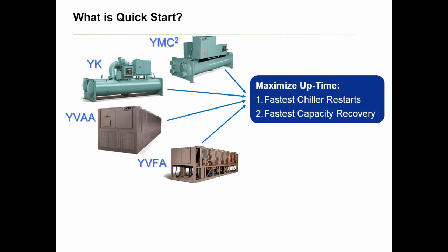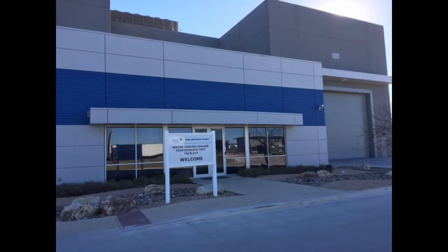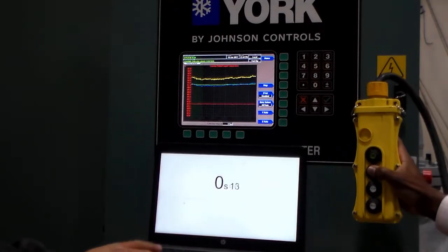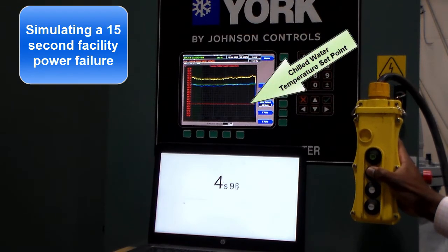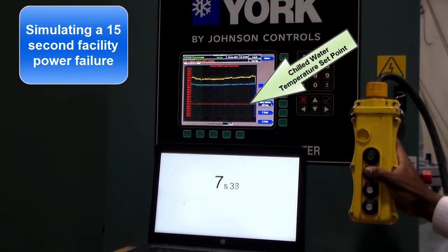To better explain, let's take a look at it in action at the Customer Center of York's Chiller Manufacturing Facility in San Antonio, Texas. Here we're conducting a power loss simulation on a 530-ton or 1865-kilowatt YMC-squared chiller for a York customer.